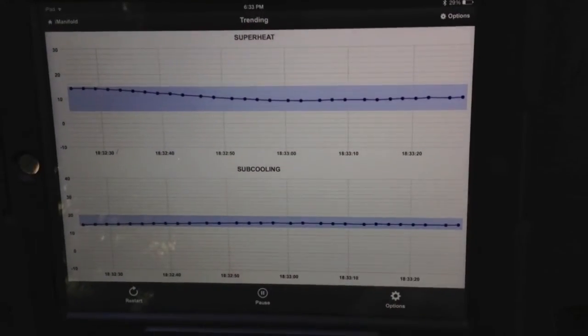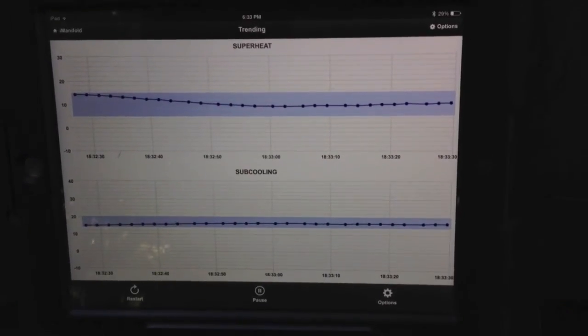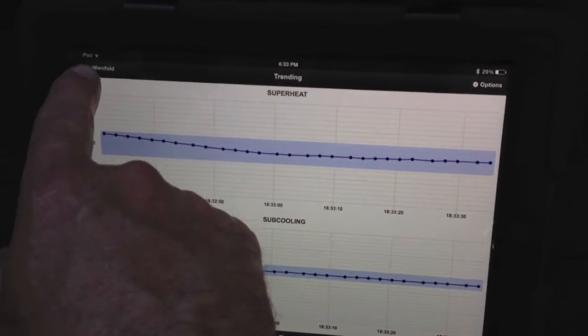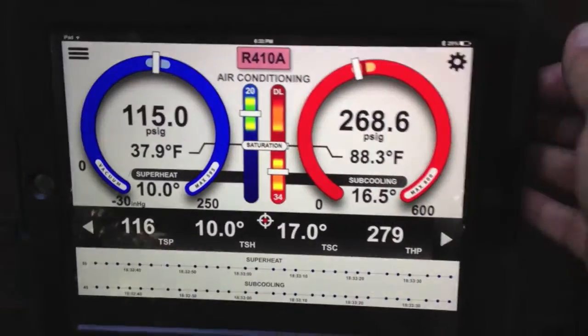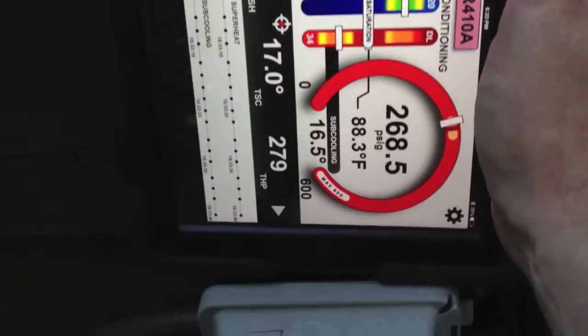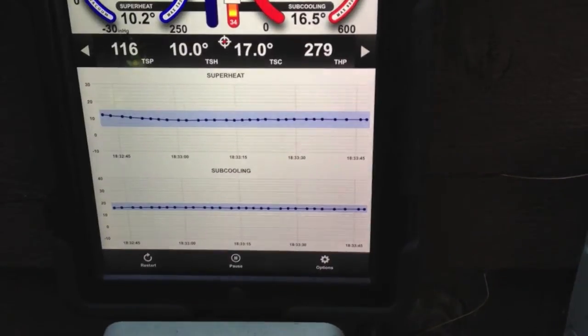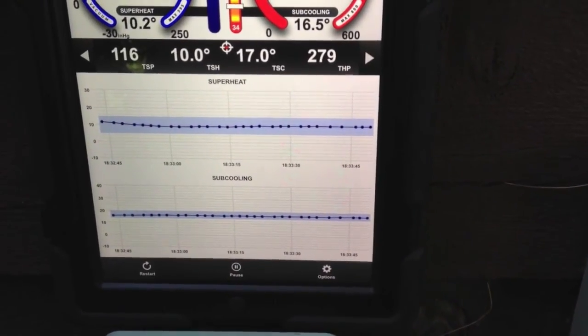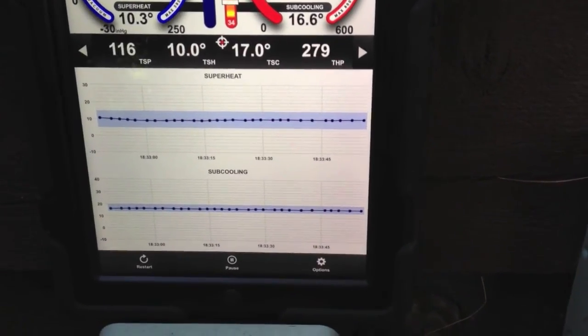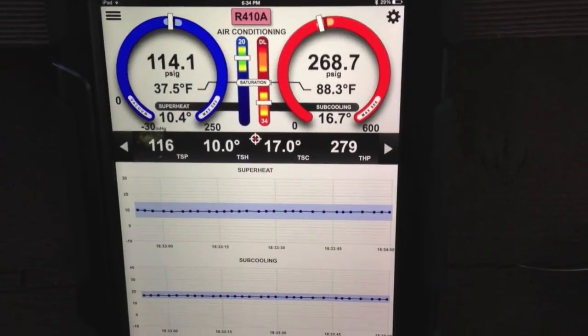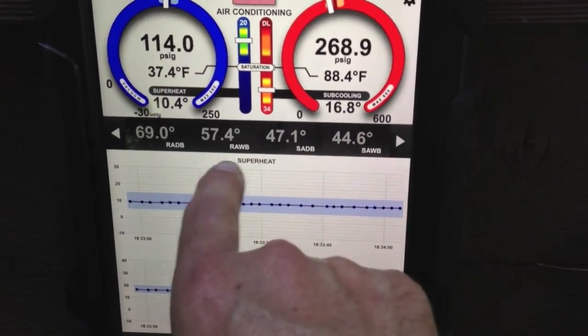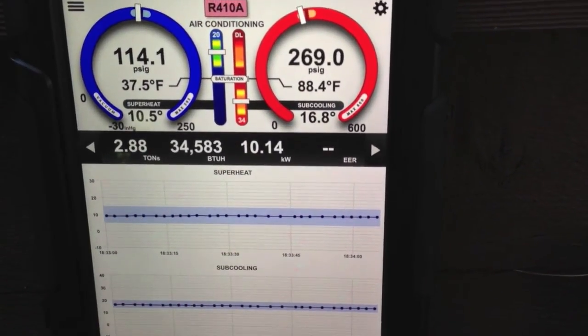Checking superheat and subcooling — those are right in line with where they should be. That's a little bit of what trending does, and I hope you got something out of this. I think it's one of the coolest features we have on the iManifold to date. For me, it not only gives you a chance to see if things are stable and doing what they're supposed to do, but it's also a great teaching tool. No matter how many years you have in the industry, watching the relationships and what happens helps you understand better what your air conditioning system is really doing. This is Jim Bergman for Imperial Tools — thanks a lot for watching.